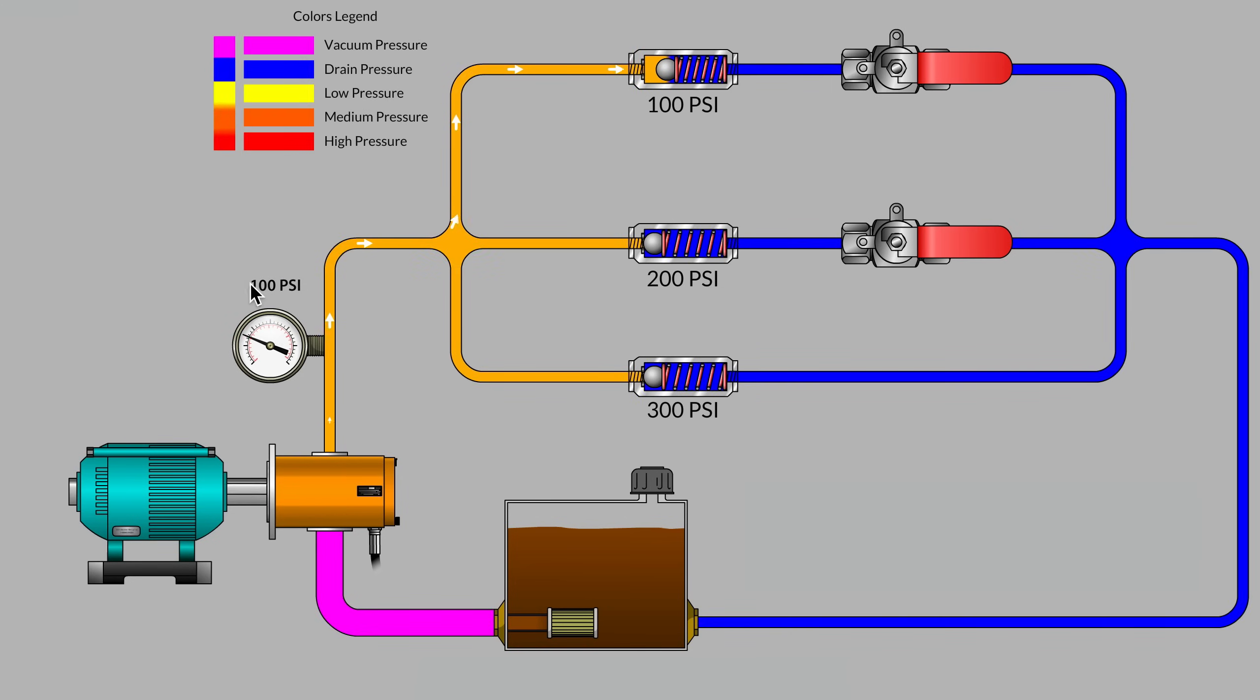If you guessed 100 psi as the correct system pressure, great, super, because that's our easiest path for oil to pass through the hydraulic circuit. If the hose is oversized and the only resistance is the spring and the spring-loaded check valve, it makes sense that the pump's flow will only move along the top parallel path and we would only get a 100 psi system value.